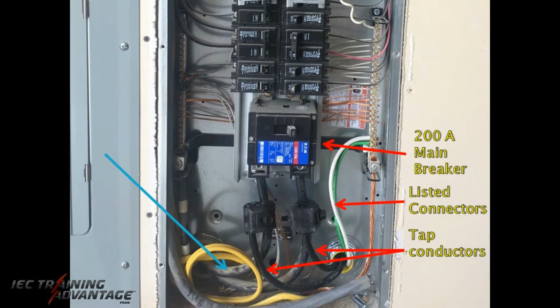We actually can't see the overcurrent protection that is protecting those first conductors that I mentioned. But this is the kind of situation that if we could see it, it would definitely reflect that the overcurrent protection matches the feeder ampacity, and these tap conductors would not be protected by that feeder overcurrent protection device.